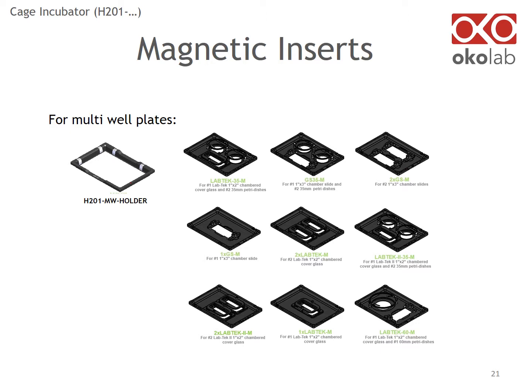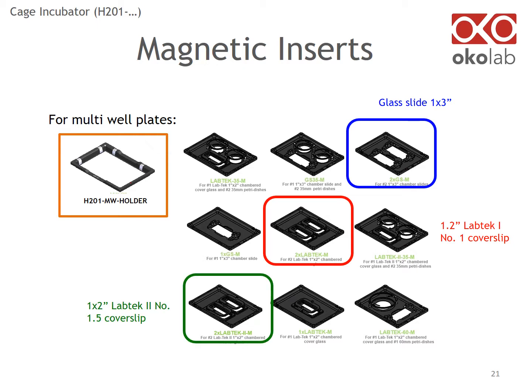Okolab chambers have built-in perfusion holes, a sliding lid, and magnetic inserts. Inserts are magnetic. For multi-well plates, you will need the holder in the orange box. If you image slides, please specify if they are 1 by 3 inches (blue box), or 1 by 2 Lab-Tek 1-chamber cover slips (red box), or Lab-Tek 2 (green box). Each requires a specific insert — using the incorrect insert will cause the sample to sit improperly and not flat.